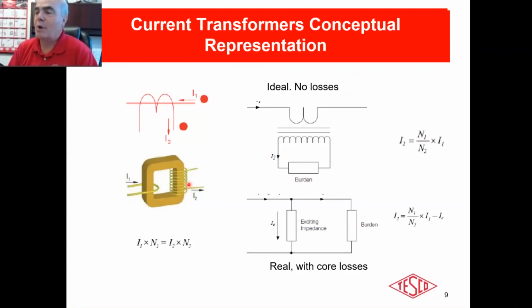Back in those days, the meters were not typically 0.3%. They were not that accurate. They were not that consistently made. They were basically all made somewhat by hand. So given that, everybody tried to go to 5 amps. We're well past that. Our CTs are much better than that. They are extremely accurate. We don't have to worry about going to 5 amps. The sweet spot of the meter is no longer 5 amps, but we're a very conservative industry, so we still do everything to 5. In Europe, you can find what they call unity transformers, which are a ratio to 1. So you would actually see an 80 to 1 transformer over there. Possibly you will also see 400 to 5s.